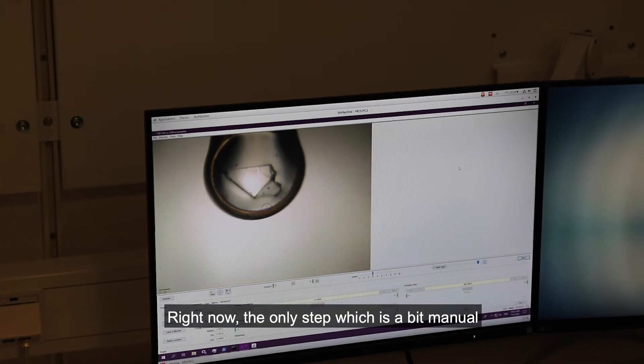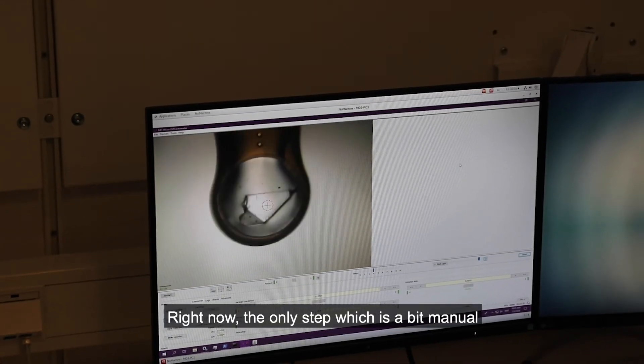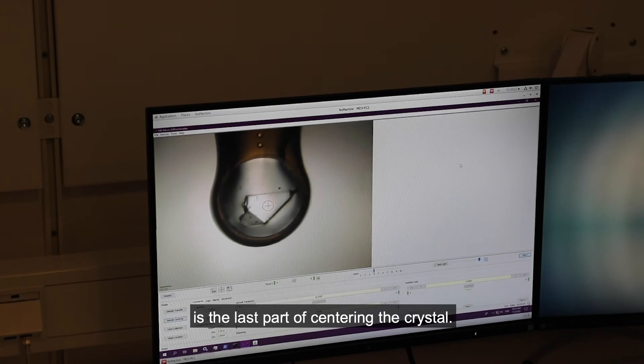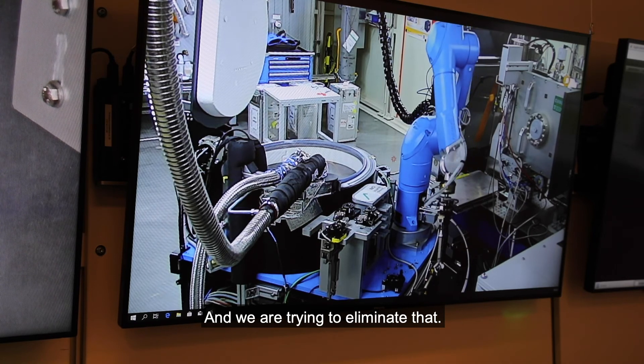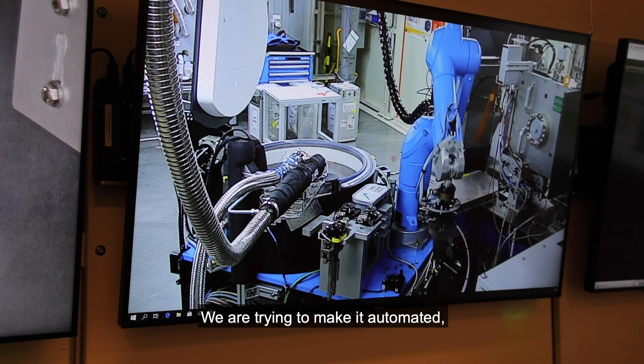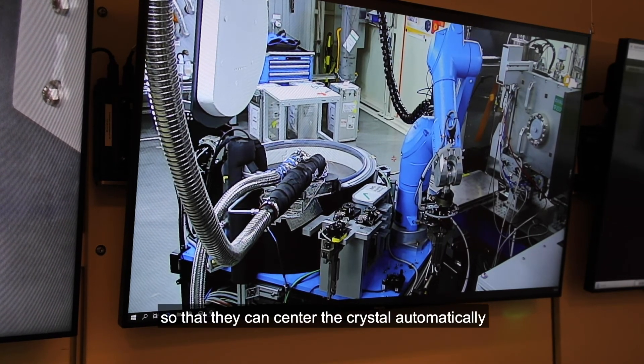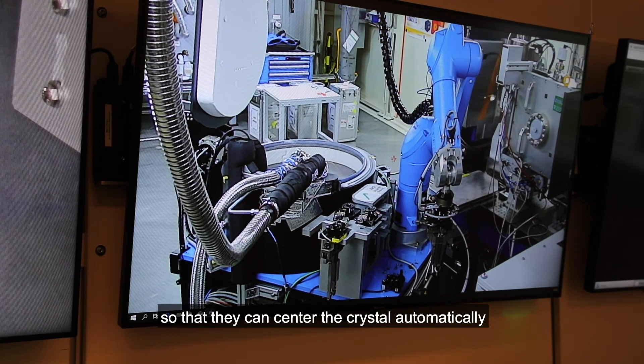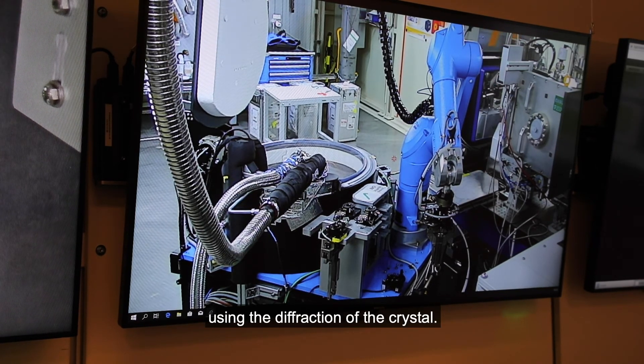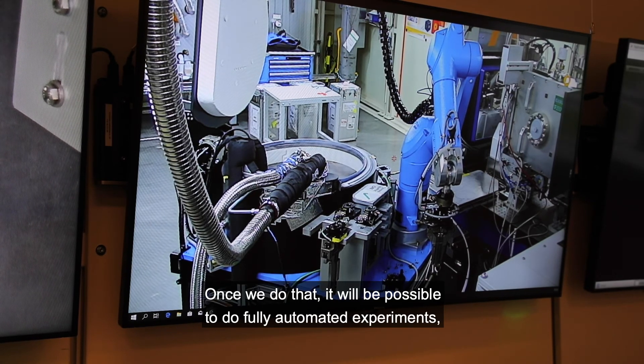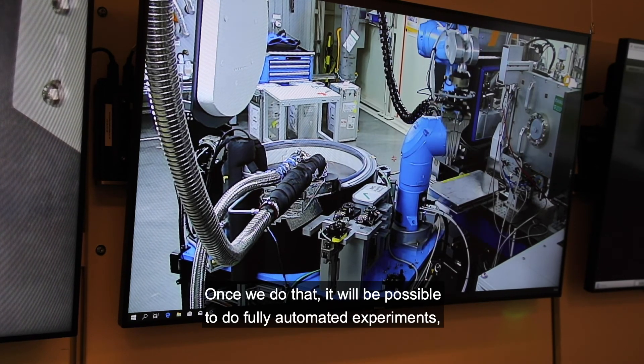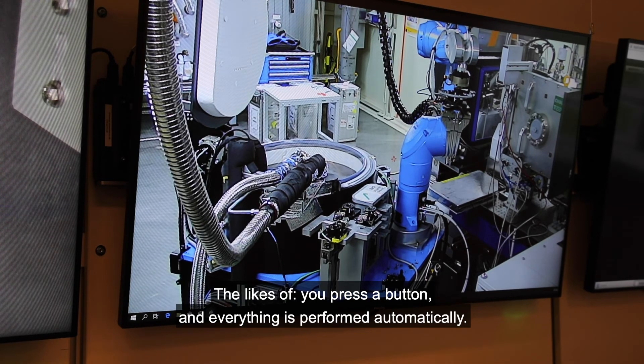So right now pretty much the only step which is a little bit manual is the last part of centering the crystal. And we are trying to eliminate that. We are trying to make it automated so they can center the crystal automatically using the diffraction of the crystal. Once we do that it will actually be possible to do fully automated experiments, like pressing a button and everything gets done automatically.